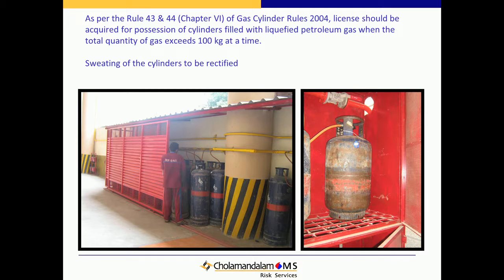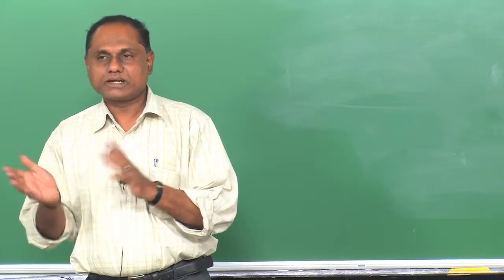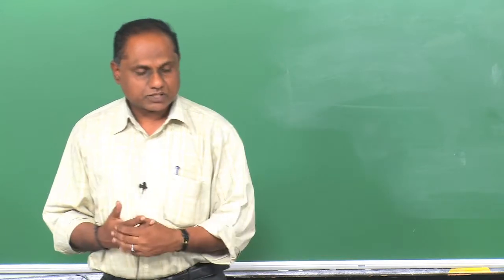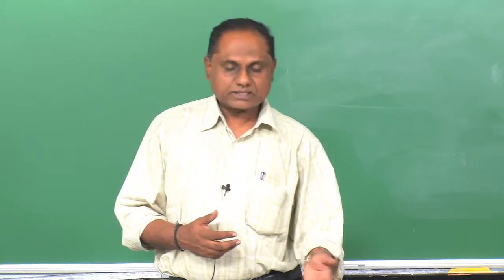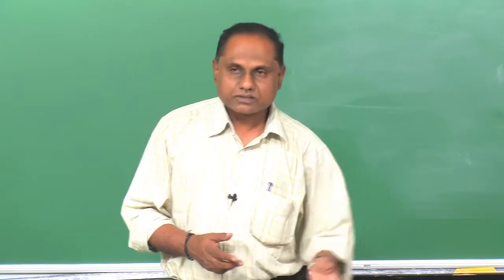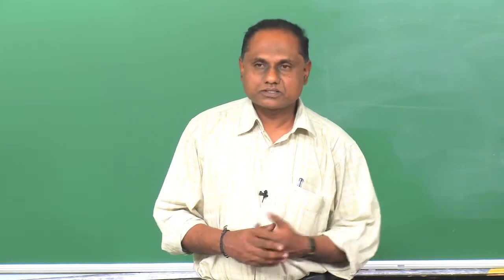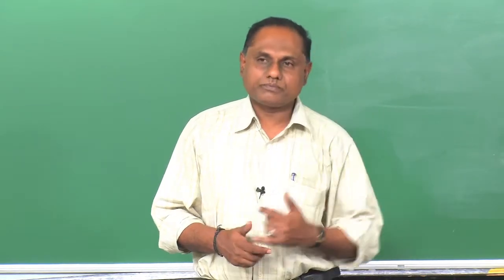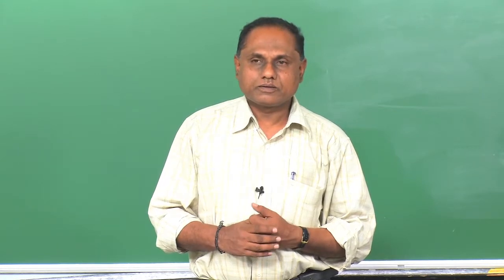As per rules 43 and 44, a gas cylinder license should be acquired for possession of this. They don't even have a license. If you have LPG cylinders above 100 kgs, you are supposed to have a license. They are storing more than 10, 11, 12 cylinders, so they are not following this. And in case of any fire, the whole building will be in danger.